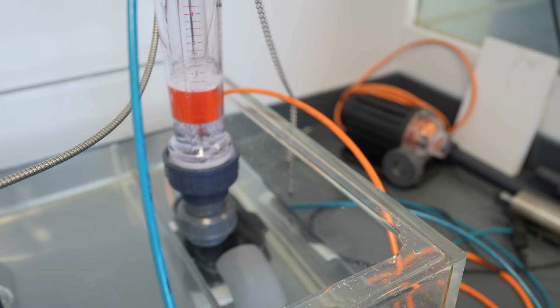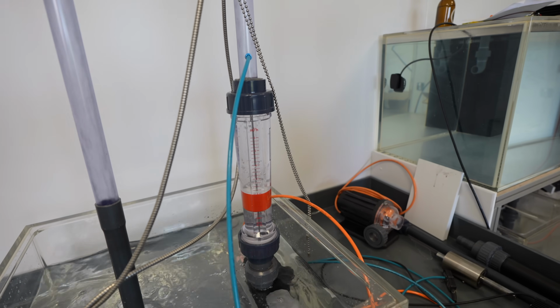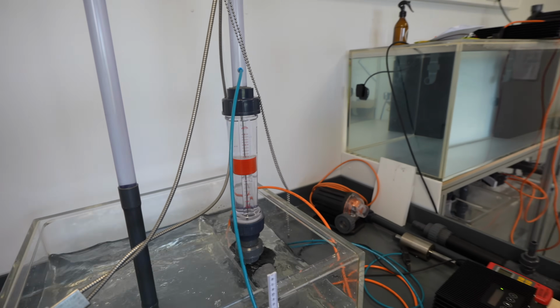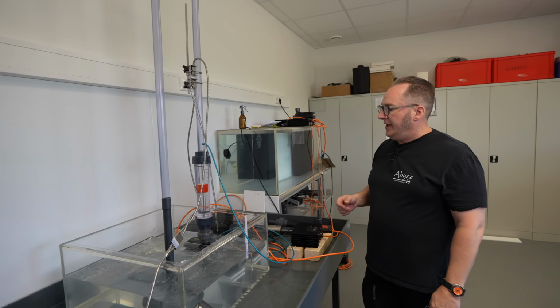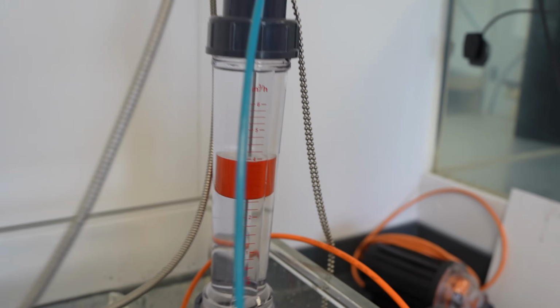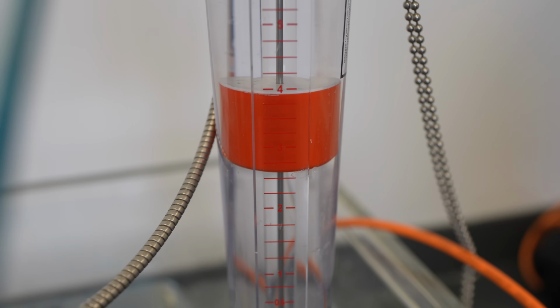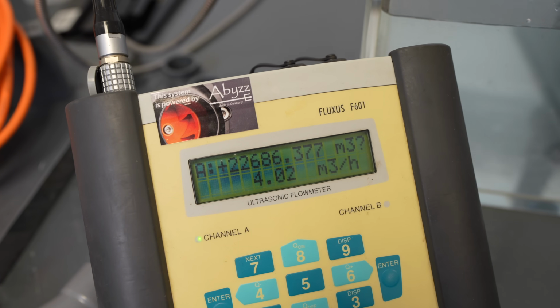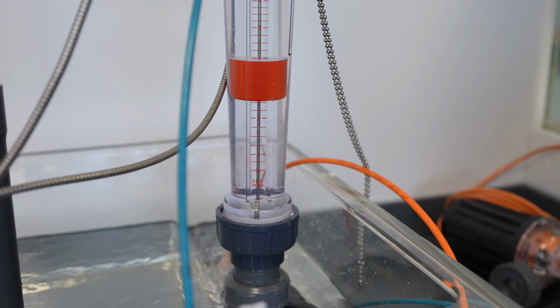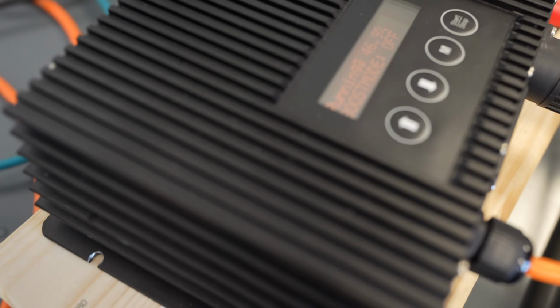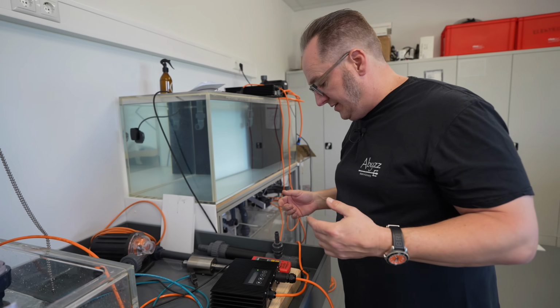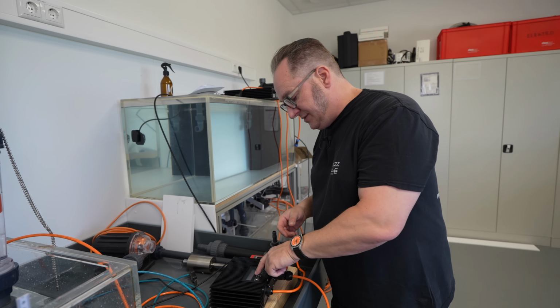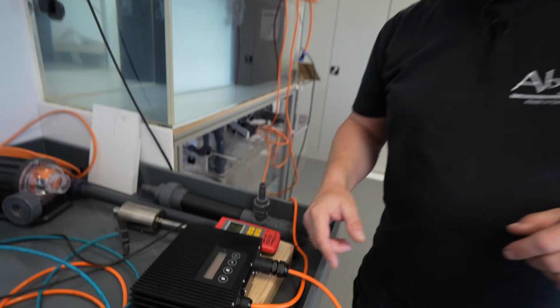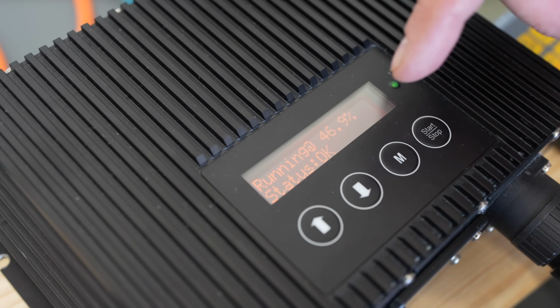Now we're starting up the pump with exactly the same value as before, 46.9%. And guess what? We have less than 4 cubic meters. The ultrasonic device still shows 4, but here we are roughly at 4, and before that we were at 5, which gives us roughly 20% loss in turnover rate with the same settings. Notice that the power just went down from 49 to 43. You'll see in a second here.